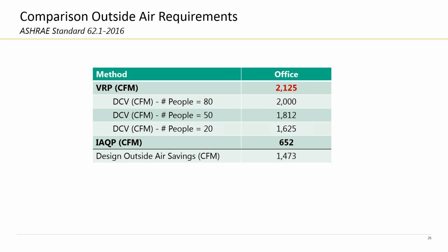Indoor air quality procedure, since you're actually addressing all the contaminants, including those that are generated from the space itself, the floor in this particular case would be 652 CFM. So over a 75% reduction is not uncommon with the indoor air quality procedure. Basically, the lower limit is typically pressurization of the building. That's what outside air is needed for, since contamination within the space of CO2, formaldehyde, et cetera, will be controlled by the air cleaning devices.